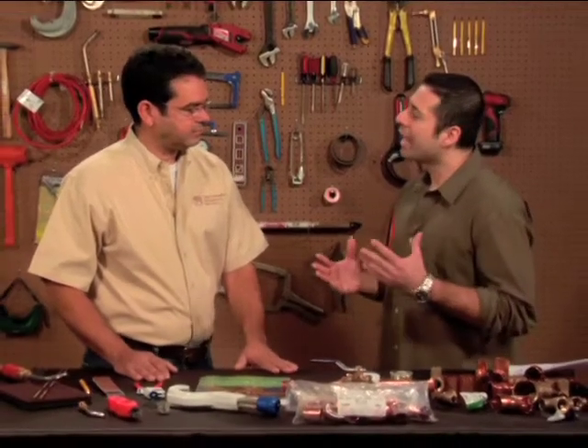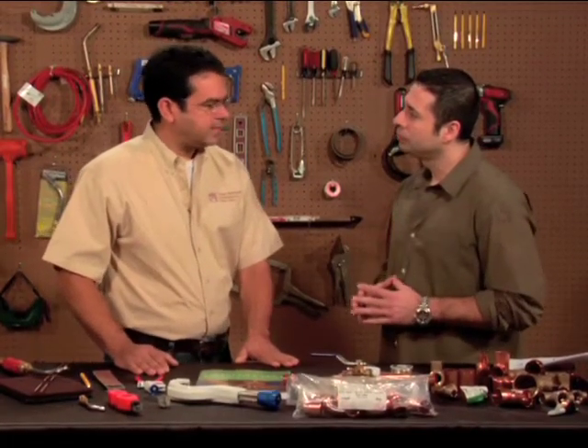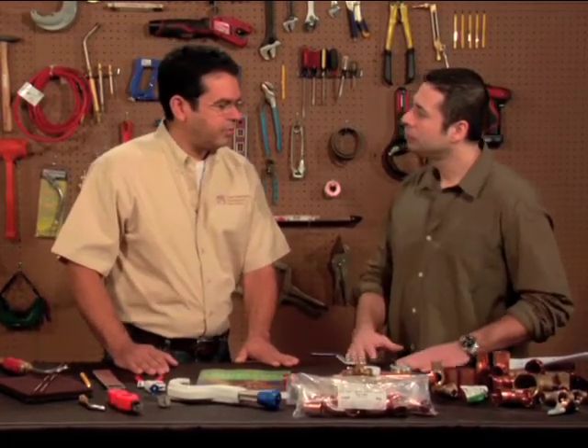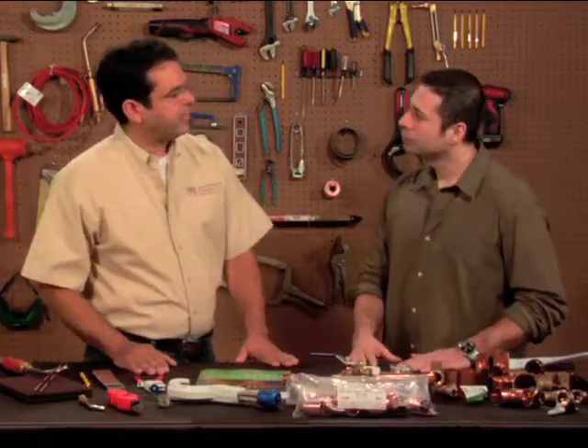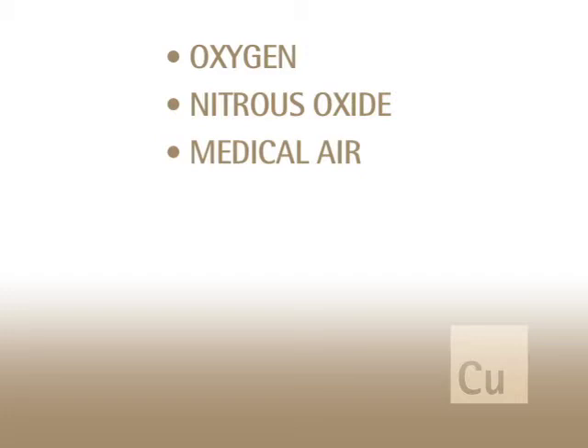To assist me today is Ron Gamuccio. Welcome, Ron. Thanks for having me, Harold. What types of gases are considered medical? Medical gas systems are used to transfer gases such as oxygen, nitrous oxide, medical air, and medical vacuum.